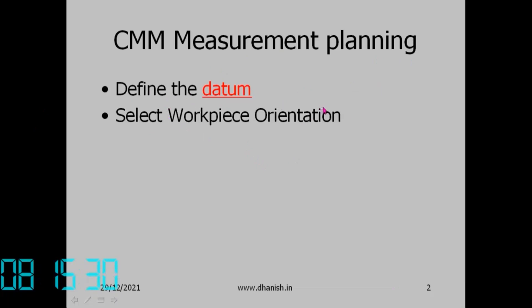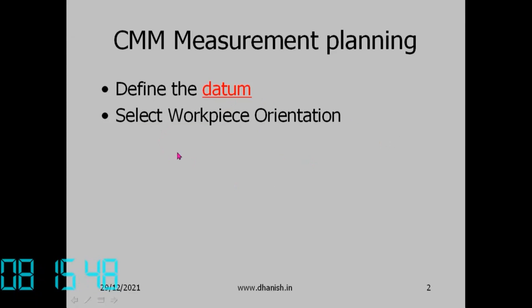When planning, first you have to study the drawing and identify which surfaces are the datum. That is why GD&T is really necessary when you are using the CMM. Then you select the workpiece orientation — how will you place the workpiece on the table.